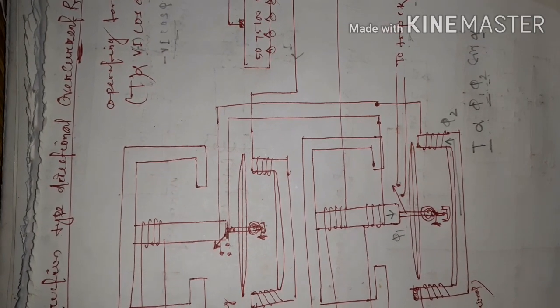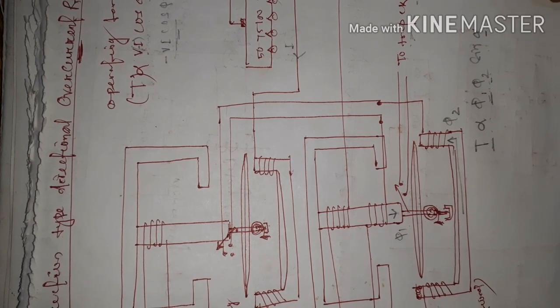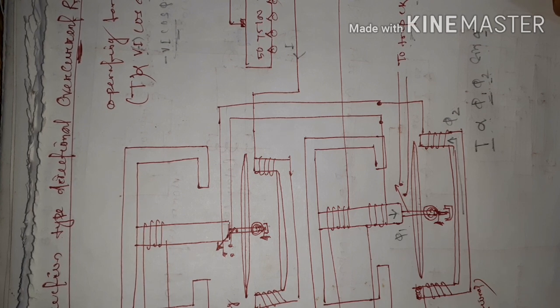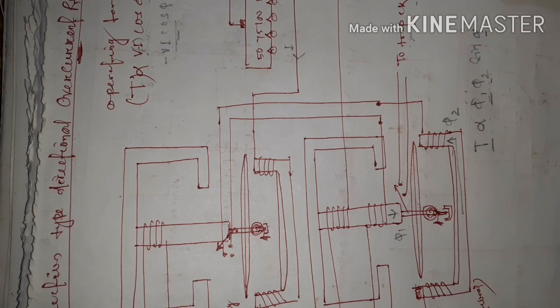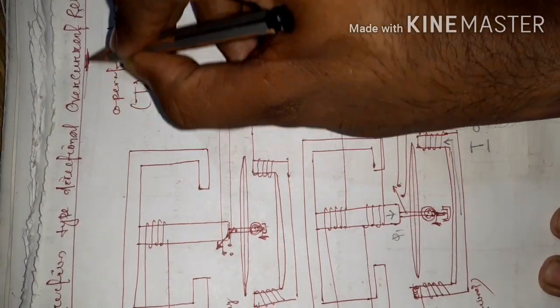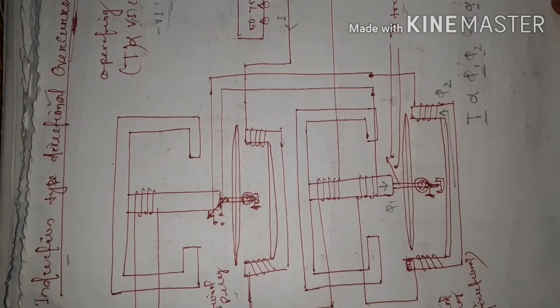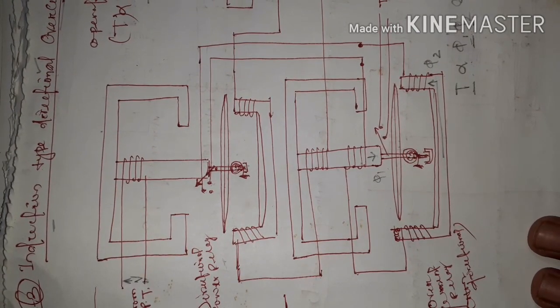Hence we can conclude that this type of relay depends upon two values: first, the magnitude of fault current, which must exceed the predetermined value, and second, the direction of fault current. Due to the magnitude of the fault current it is called overcurrent relay, and due to the direction it is called directional. Combined, it is called induction type directional overcurrent relay. It is called induction because its working principle depends upon mutual induction — when the flux links with another coil.